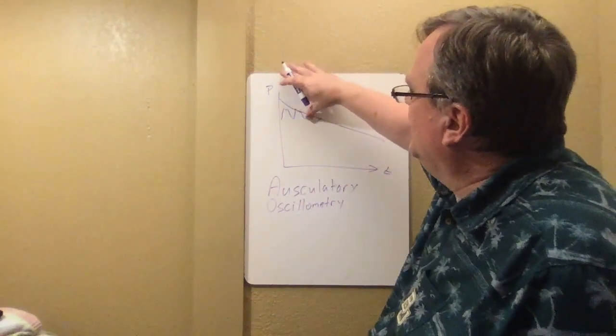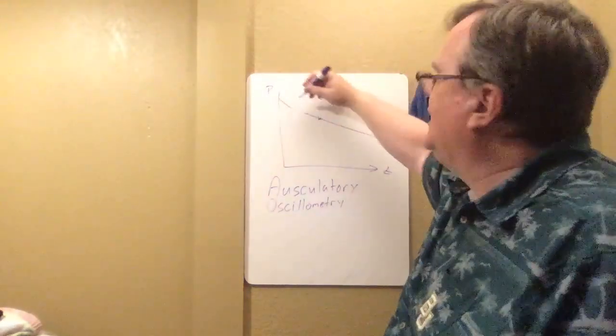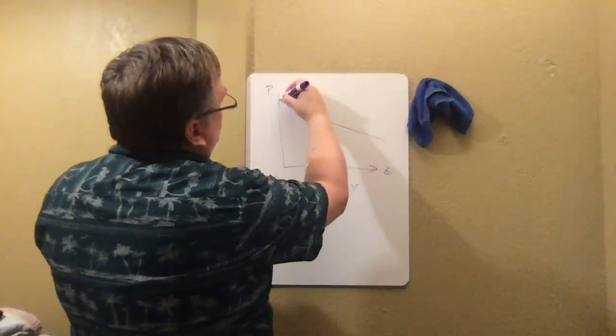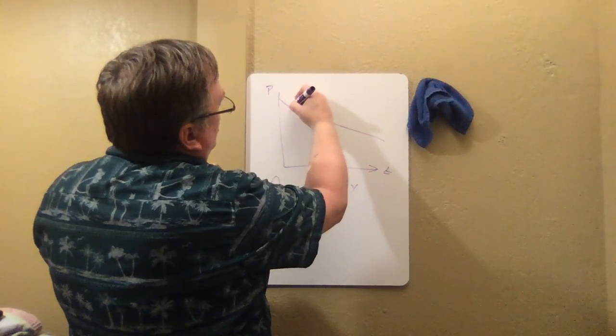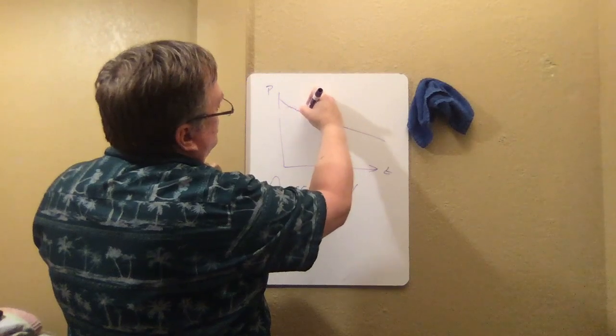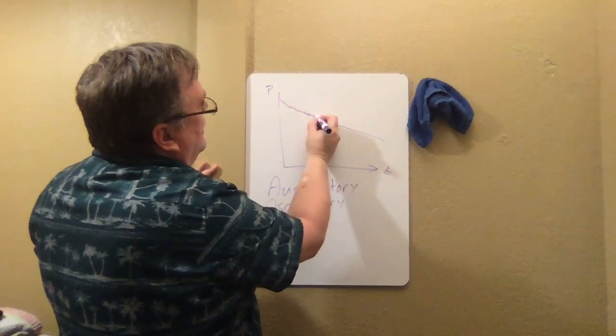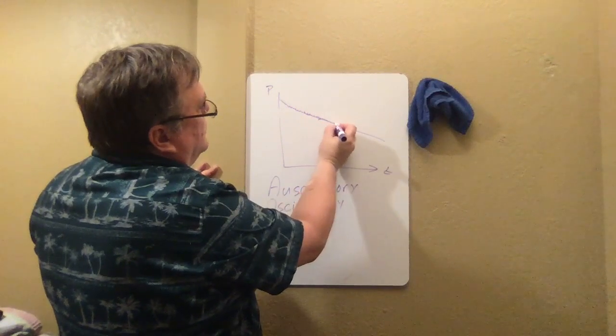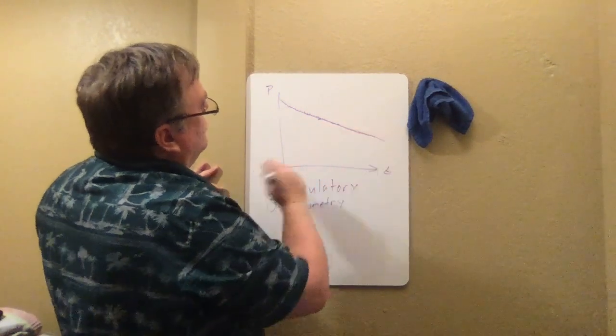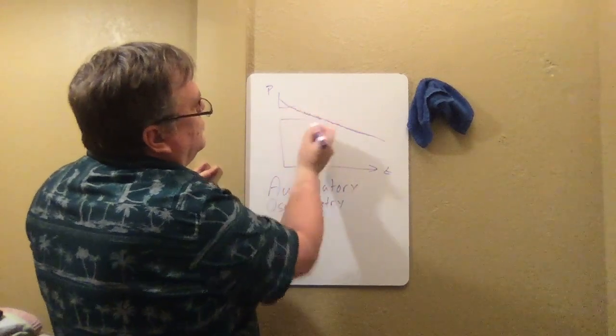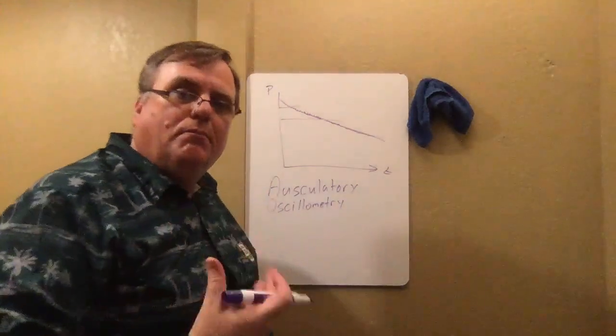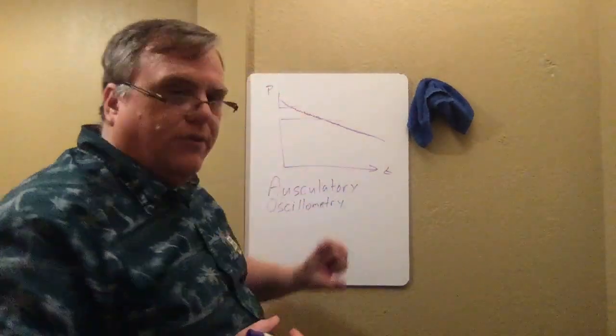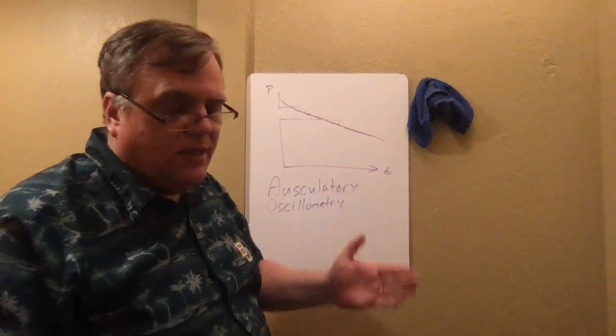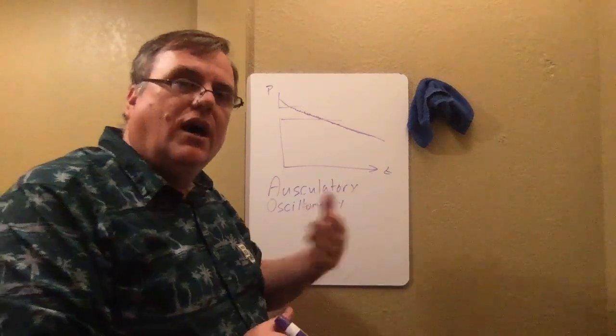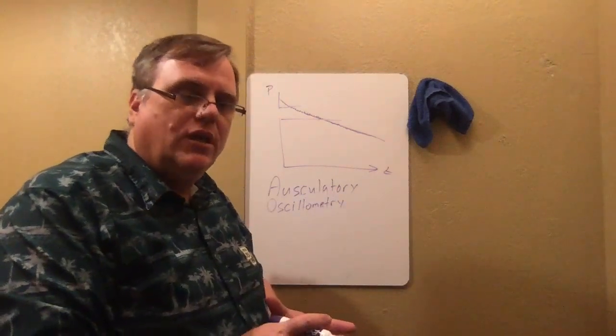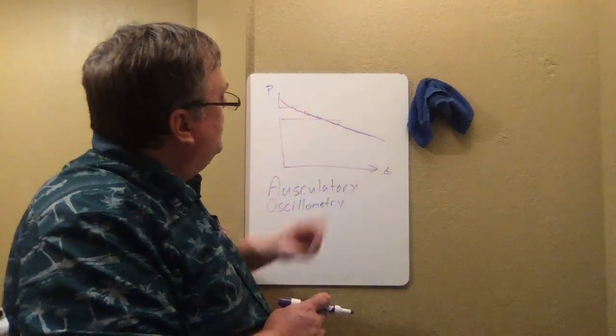When you actually look, that is the size of the actual wave. But when it gets onto this, you'll see some noise variations as the pressure's coming down. And once it gets into this range, you'll see these little pulses, which are that wave going through. They'll die off as they come down, but there's always some noise going down. But right in the range where your heartbeat is, they're bigger. That bigger wave in here, you can pick up with a very, very sensitive pressure meter. A human's not going to do it eyeballing it, but I can put a machine on that's going to measure those oscillations very quickly and very accurately to find out what these look like.